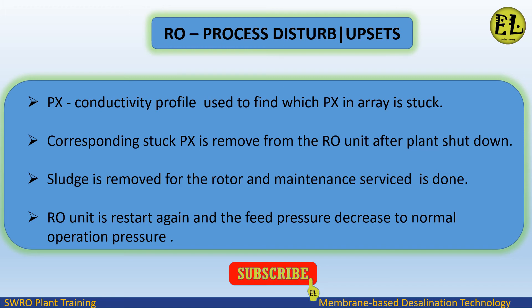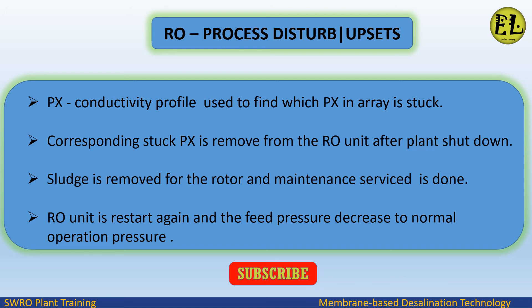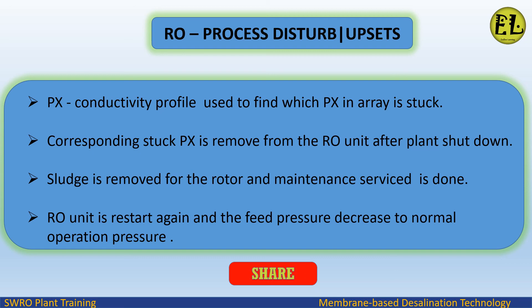The corresponding stuck PX is removed from the RO unit after plant shutdown. Sludge is removed from the rotor and maintenance service is performed. The RO unit is then restarted and the feed pressure decreases back to normal operating pressure.